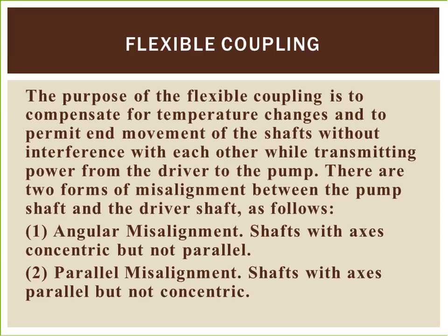There are two forms of misalignment between the pump shaft and the driver shaft as follows. One, angular misalignment, which is the shafts with axes concentric but not parallel. Two, parallel misalignment, which is the shafts with axes parallel but not concentric.